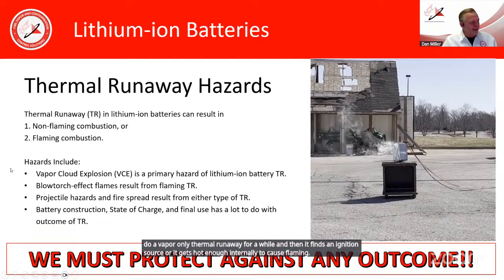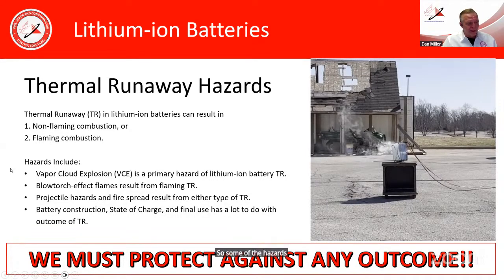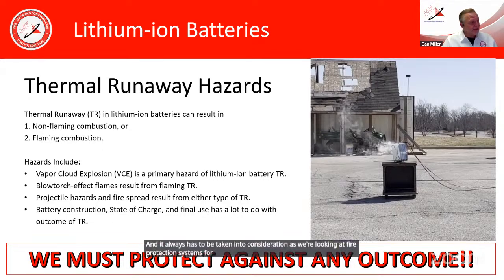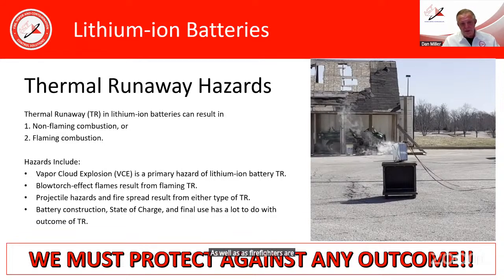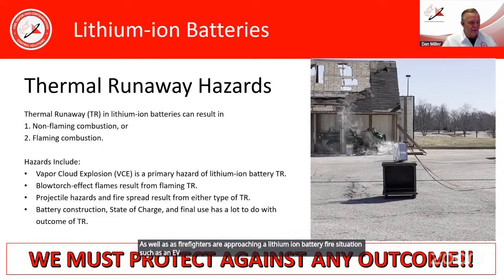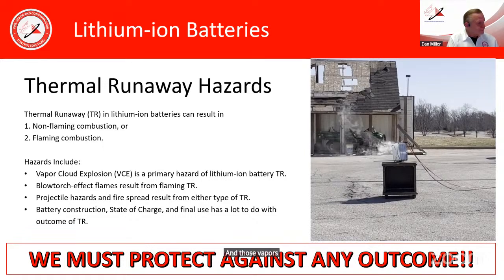Some of the hazards as a result include vapor cloud explosion. Vapor cloud explosion is a primary hazard of lithium ion battery thermal runaway, and it always has to be taken into consideration as we're looking at fire protection systems for lithium ion batteries, as well as firefighters approaching a lithium ion battery fire situation, such as an EV inside of a garage where they don't have good visibility and those vapors might be confined.